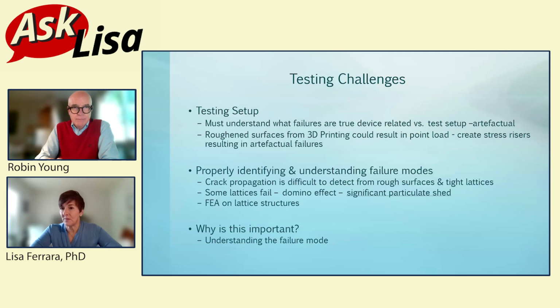You've got roughened surfaces on the titanium, especially when they first came out. They were doing EBM and laser, but those roughened surfaces weren't as perfected at that point, and we were trying to identify cracking. As you all know, for interbody cages, we run static and dynamic compression, compression shear, and torsion. Well, you have to inspect, and we always did. Every implant was inspected prior to testing, whether it was printed or not.